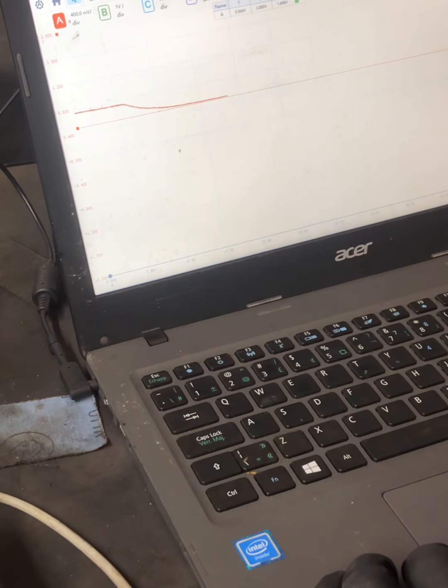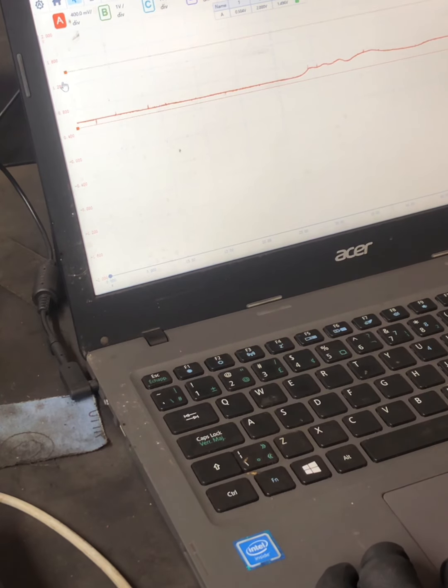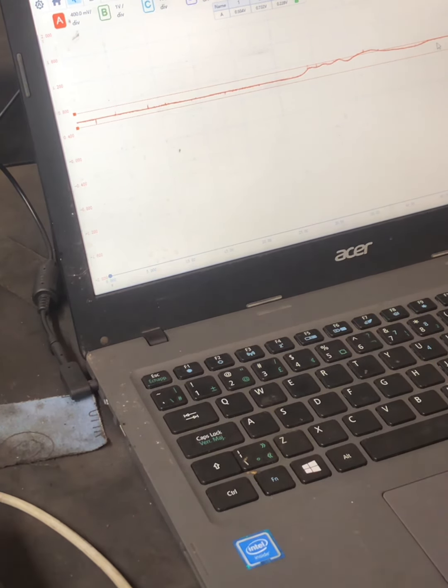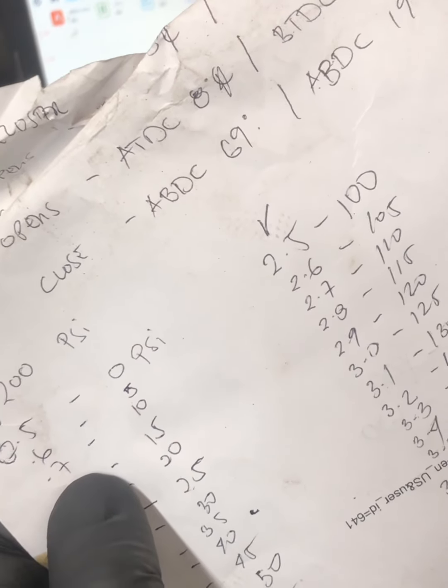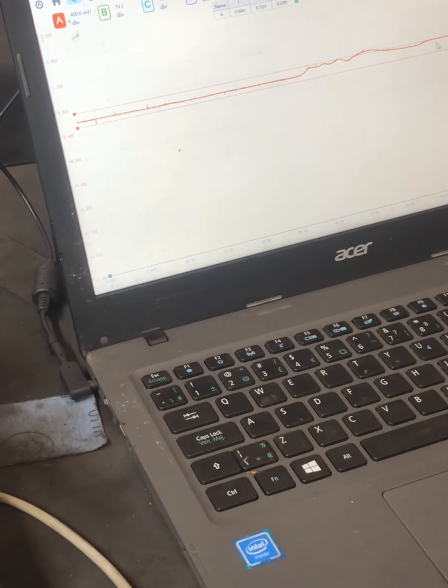So I'm just gonna stop this and go back. At this point here, this is where I go to 1000 RPM. So that's 0.5 to 0.7, and our measurement is more or less 10 psi. That's really not good, because the spec says 14 psi.